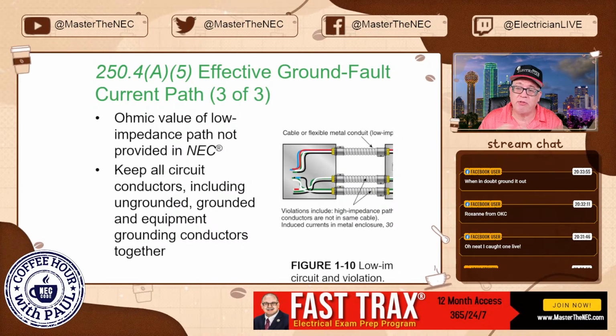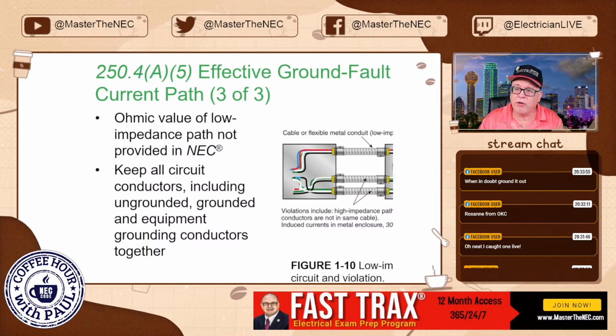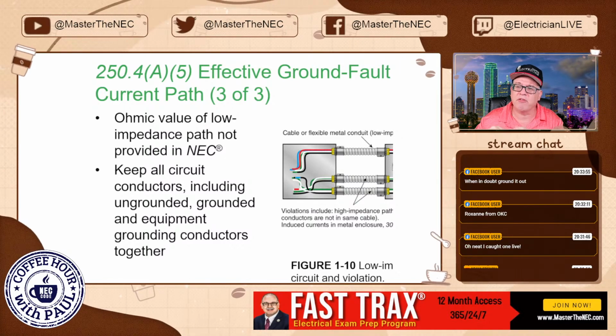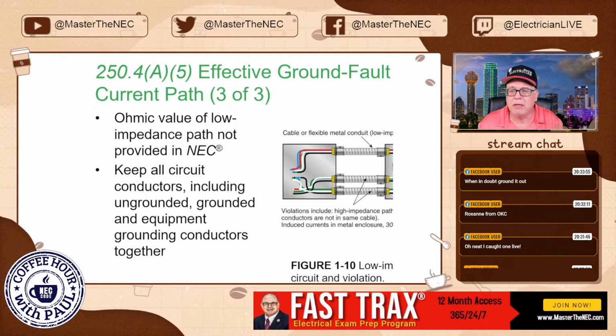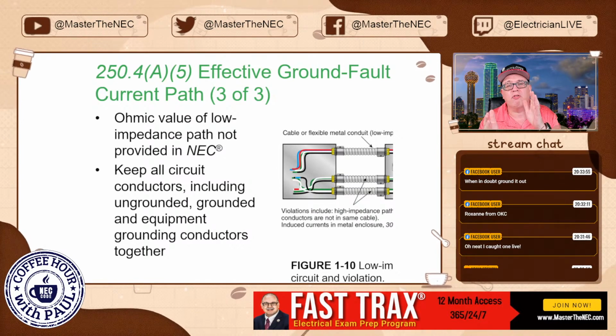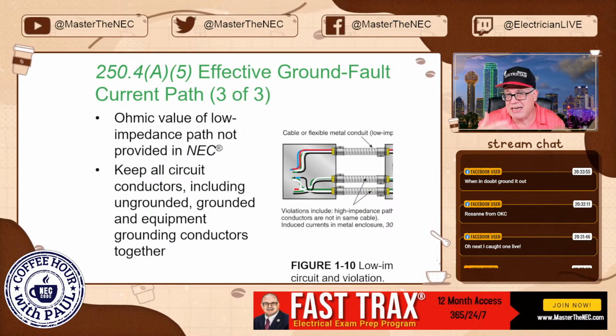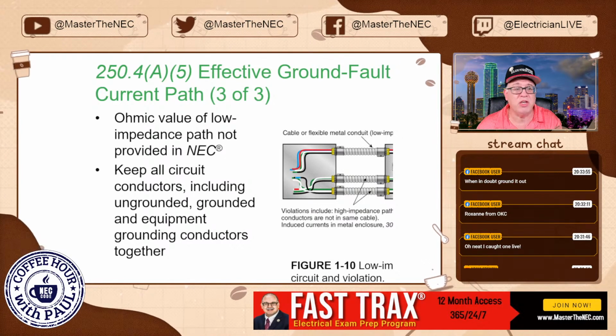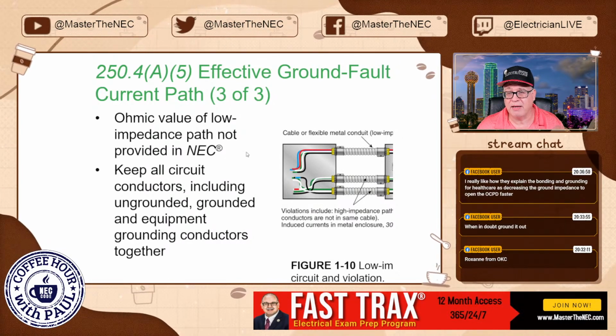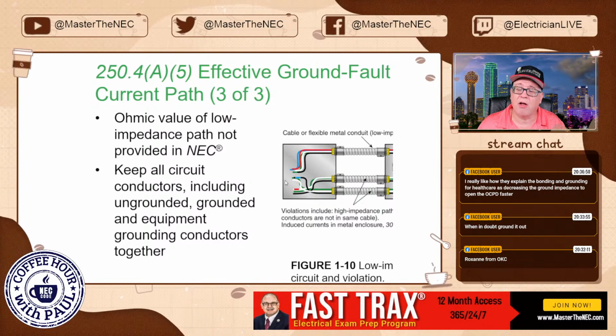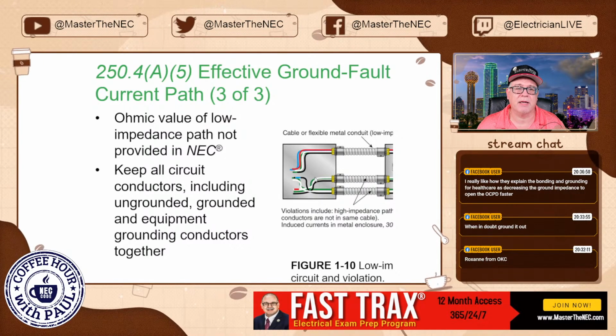Now, heaven forbid you have any ferrous metal, whether it's the wiring method that's ferrous metal or the cabinet is ferrous metal, and you do this, you create these induced currents, you're going to have induced heating as well. It's something you do not want, okay? You will certainly start melting down insulation, things like that, okay?